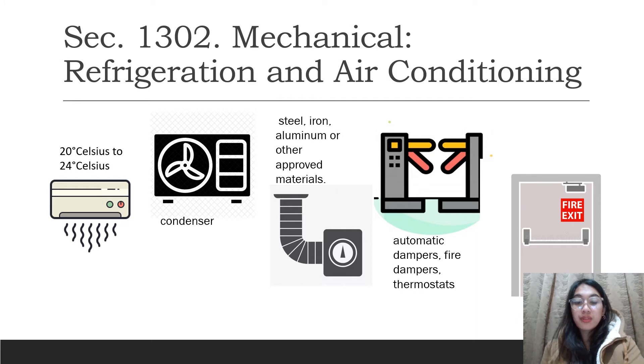Fire doors and fire dampers shall be arranged to close automatically and remain tightly closed upon the operation of a fusible link or other appropriate actuated device located where readily affected by an abnormal rise of temperature in the duct.